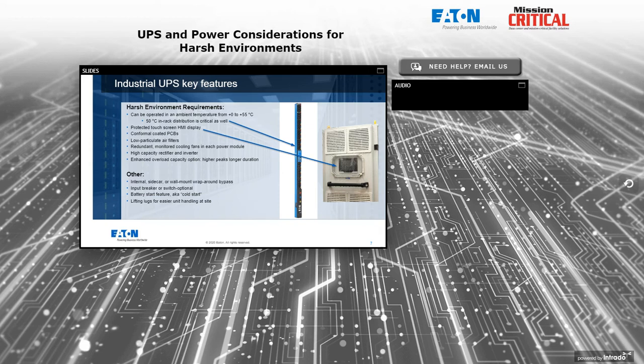Same thing for the inverter: a higher capacity inverter that takes the DC from the battery or the rectifier and converts it to AC for the UPS output. It needs to be rated to handle perhaps higher inrushes, motor loads, the presence of variable frequency drives, etc., on the output, and a load that changes rapidly. This is a little more of a challenge than it would be, for example, in a UPS that sits in a data center or a network closet, where the load is relatively constant day in and day out. These industrial loads tend to be widely variable and have some very, very high inrushes. That needs to be taken into account, again, at the system design stage.